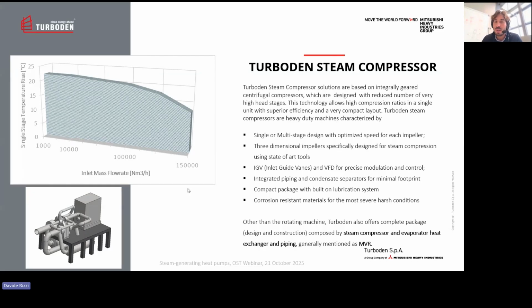Regarding control, which I think is very important to speak about, especially when dealing with industrial players, the steam compressor has to be controlled to follow the process needs, and we have two types of control. We can act on the inlet guide vane, basically the guide vane at the beginning of each stage of the compressor, to modulate the flow rate, and then the speed.